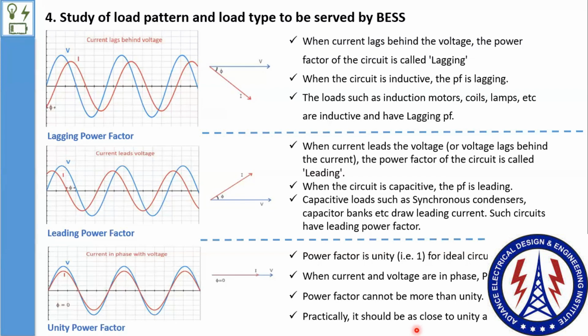If you design the system so that your power factor stays within a certain range — in India, we prefer designing above 0.92, typically between 0.92 and 0.98 or 0.99 — this is an allowable limit for injecting power into the grid, keeping grid functionality stable.